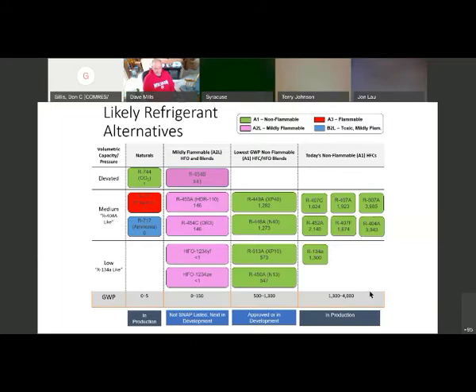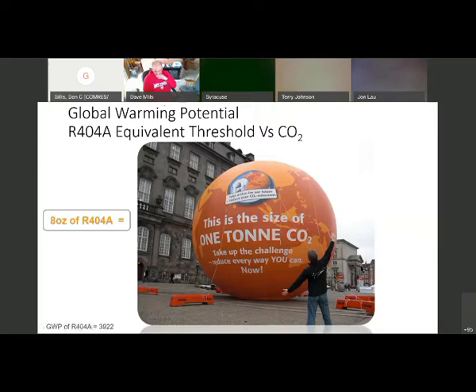The natural refrigerants — CO2, R290, and ammonia — are the 'perfect refrigerants,' if you will. At the bottom you'll see the global warming potential. The difference between a high and low GWP refrigerant is like something breaking up in 11 years versus 11 days — I'm using that as an analogy; those aren't real numbers. One ton of CO2 is the equivalent of eight ounces of 404A. The global warming potential for 404A is approximately 3,922.